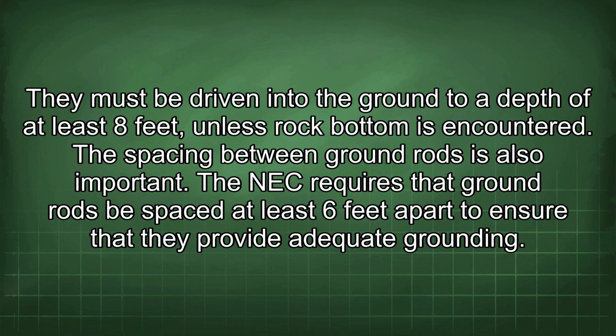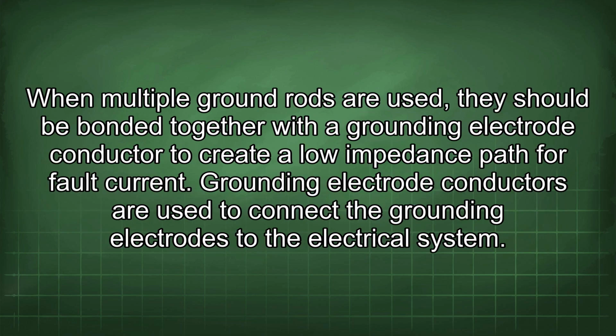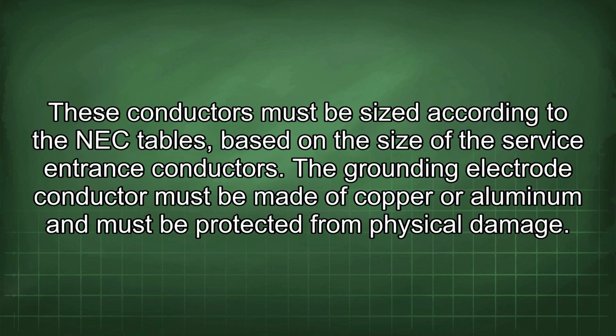The NEC requires that ground rods be spaced at least 6 feet apart to ensure that they provide adequate grounding. When multiple ground rods are used, they should be bonded together with a grounding electrode conductor to create a low impedance path for fault current. Grounding electrode conductors are used to connect the grounding electrodes to the electrical system. These conductors must be sized according to the NEC tables based on the size of the service entrance conductors. The grounding electrode conductor must be made of copper or aluminum and must be protected from physical damage.